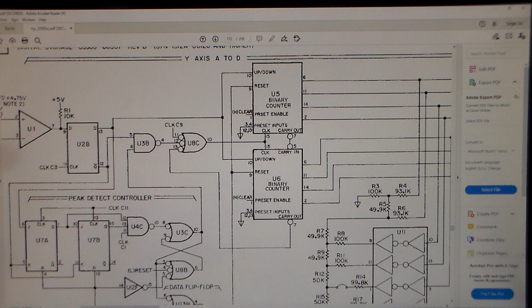I've just replaced the counter for the low order nibble of the A to D converter for the Y-axis, and it looks like everything's working fine now. It does need a bit of adjustment - the baseline has to be centered on the bottom line of the graticule, and the frequency adjustments need tweaking, I think. But essentially this unit's working again.